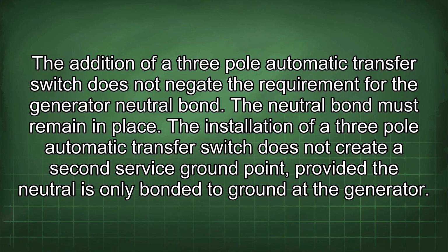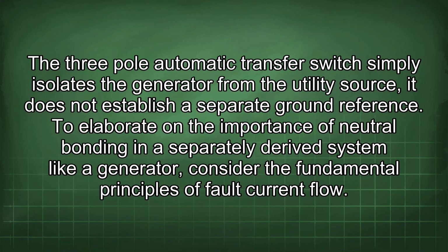The installation of a 3-pole automatic transfer switch does not create a second service ground point, provided the neutral is only bonded to ground at the generator. The 3-pole automatic transfer switch simply isolates the generator from the utility source. It does not establish a separate ground reference.